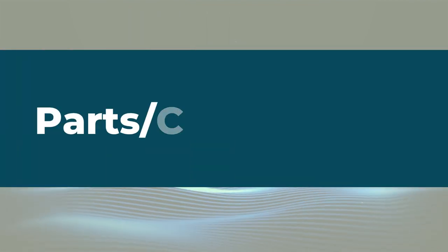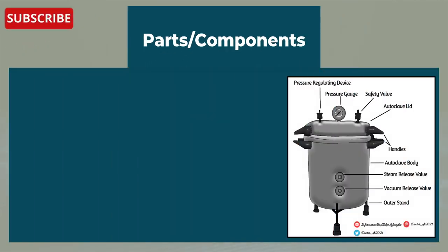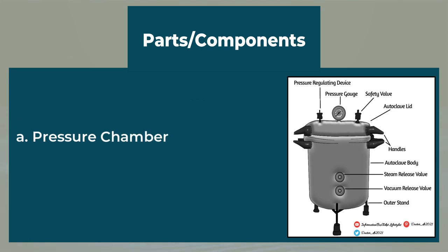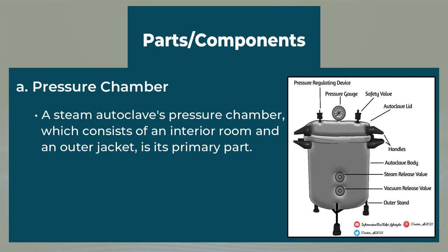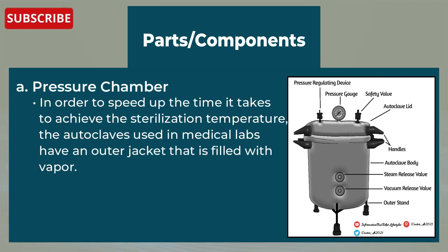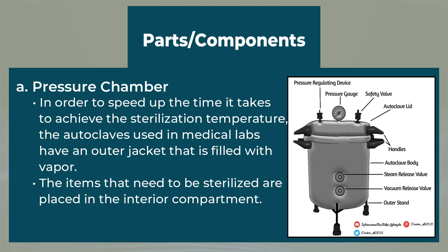Let's head to the autoclave parts or components. The pressure cooker type or laboratory table autoclaves are the most basic types. The various elements and components of an autoclave are described. First, we have the pressure chamber. A steam autoclave's pressure chamber, which consists of an interior room and an outer jacket, is its primary part. The outer compartment is made of an iron case and the interior chamber is made of stainless steel or gun metal. The autoclaves used in medical labs have an outer jacket filled with vapors to speed up reaching the sterilization temperature. The items to be sterilized are placed in the interior compartment.